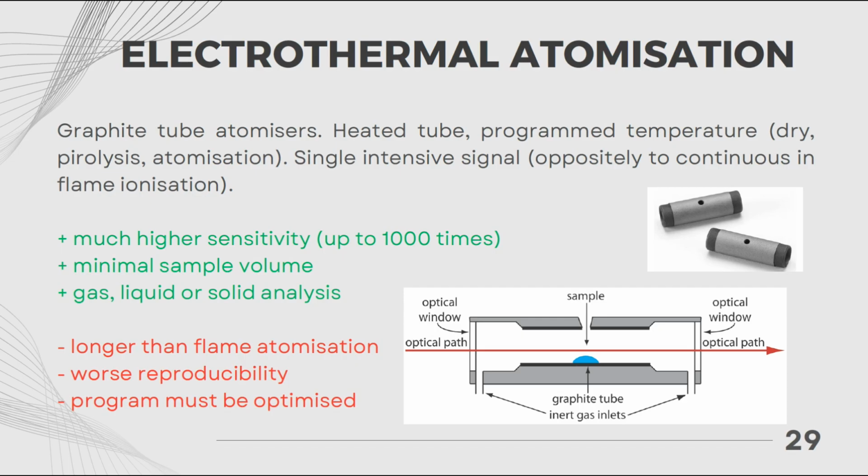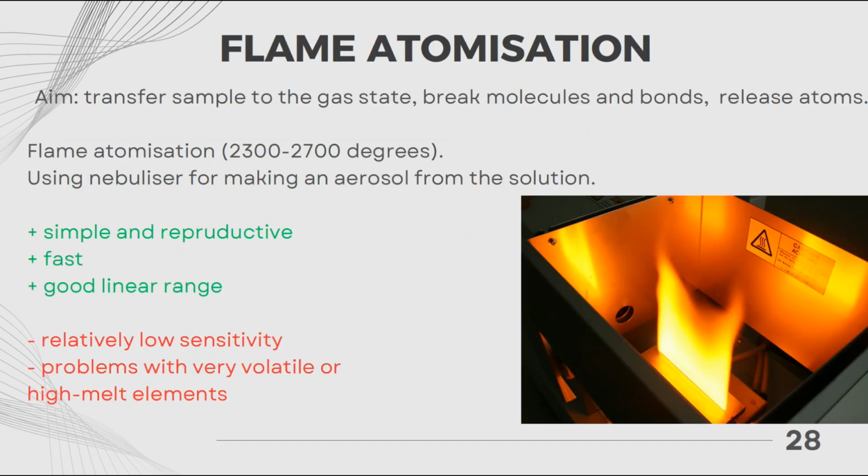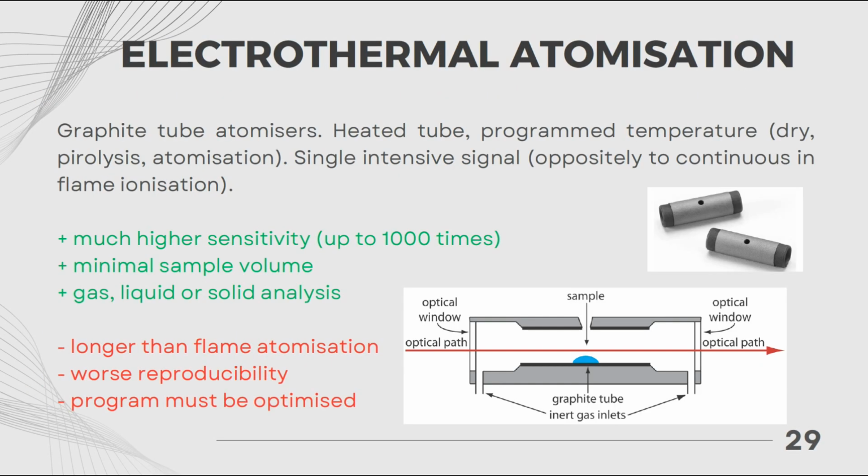And also you need minimal sample volume, which is sometimes also a good advantage. When you are limited with a sample volume, you may use a really small amount. And oppositely to flame atomization, where you use solution, which will be then nebulized, in case of electrothermal atomization, you may use gas, liquid, or solid analysis, which gives you some freedom, which neglects some sample preparation, and it's good.